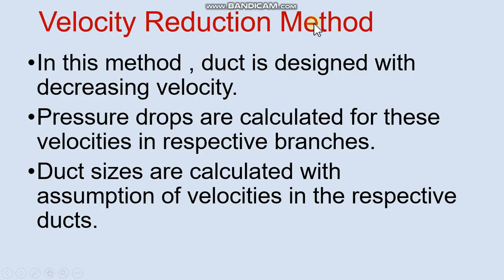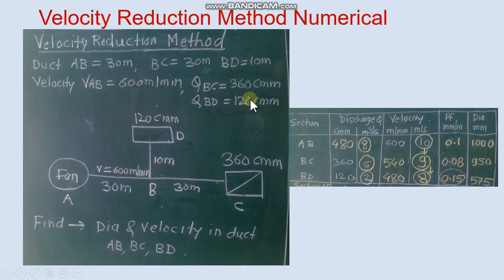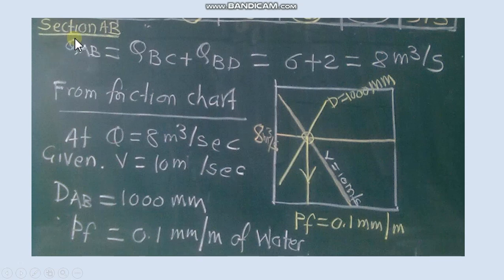Second method is velocity reduction method where duct is designed with decreasing velocity. So here we will take same problem statement. In section AB we know discharge. From friction chart velocity and discharge we get diameter and PF.